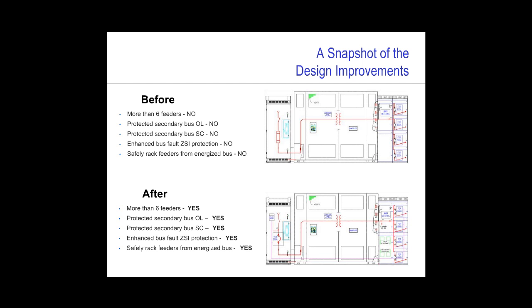First, we can have more than 6 feeders. The 6 circuit rule doesn't apply anymore because I have secondary bus protection. And also because there's secondary bus protection, I have both overload and better short circuit protection of that bus. We've added zone selective interlocking, or ZSI protection, in this substation, allowing us to trip the nearest upstream breaker to the fault with no intentional delay.